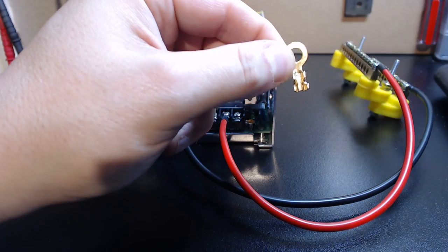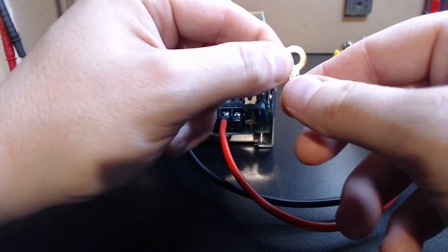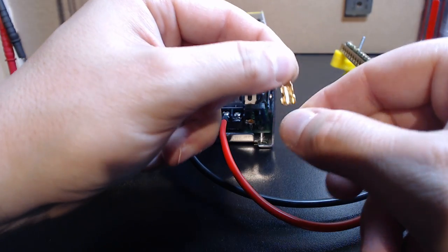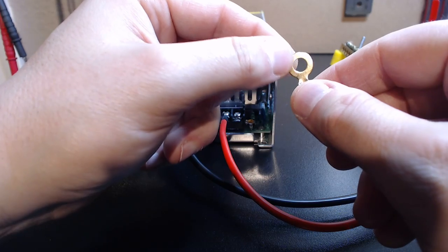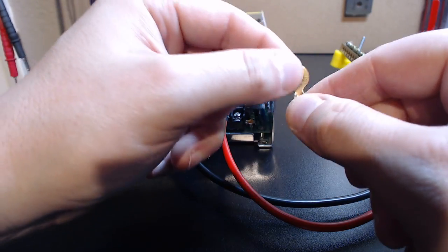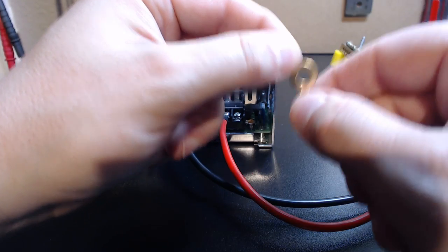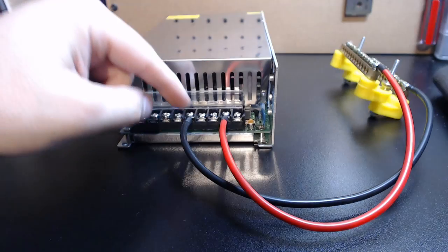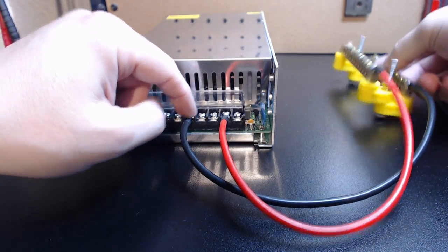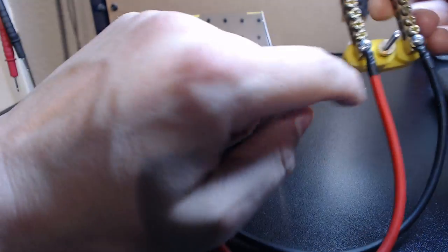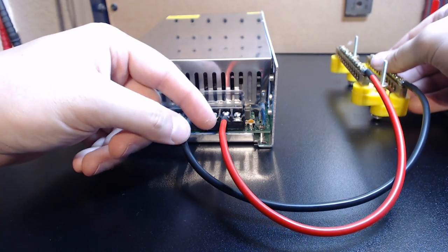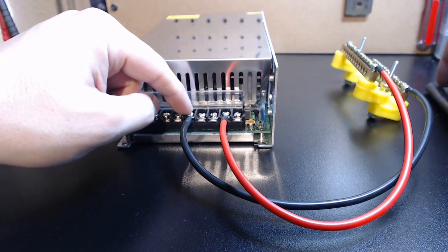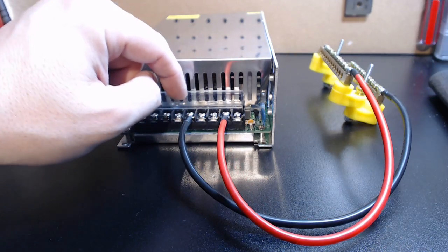But I always use ring terminals. And the reason I do, I don't like the fork terminals because if they're ever loose, now again I'm just talking safety here. If they ever come loose, the fork can slide out. With a ring terminal, even if the screw is loose, it doesn't come out. I use ring terminals on all assemblies you see here. These are ring terminals. So nothing can pull out. You'll destroy the wire before anything will pull out, even if the screw is loose. So that's safety, that's integrity.